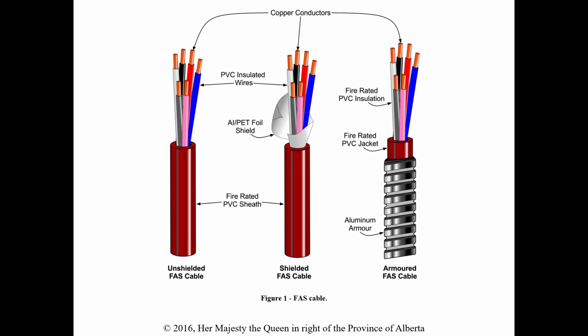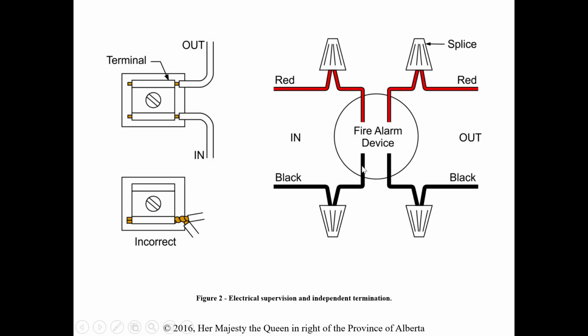They start talking about FAS cables, so you can have unshielded, shielded, or an armored. So these are fire alarm cable that we commonly will see in fire alarm installation, so fire alarm and signal cables. So it's just good to have a look at these and see exactly what they look like in case you've ever come across them.